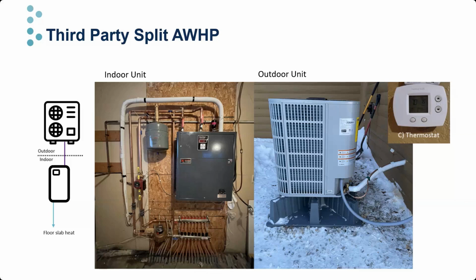The IDU on the left is the NorAir unit that simplifies connections to that of a boiler and is also produced by a well-known boiler manufacturer in Minnesota, Electro Industries. You can also see some of the existing connections to the home's in-floor hydronic system here, with the hydronic manifold mounted just below the IDU in the left image, with tubing going straight into the slab from there. Next slide.